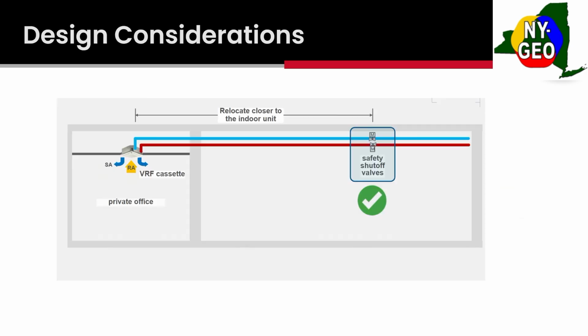Another thing that's going to be coming down the road as you get selections from your equipment reps on VRFs is the safety shutoff valves. These are field installed. They come from the manufacturer, but they're field installed. So typically they're installed right at the refrigerant changeover box. If you find that they're installed all the way back in your box and you don't meet the releasable charge, just move it closer until you meet it. And the manufacturers can provide you with how much refrigerant is between the indoor unit and that valve.